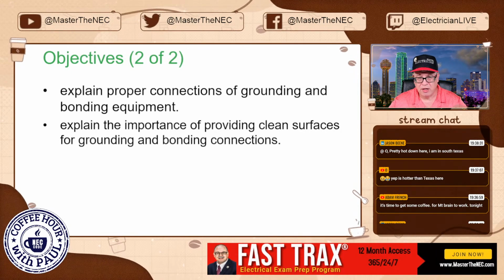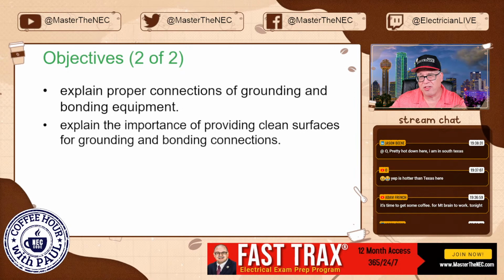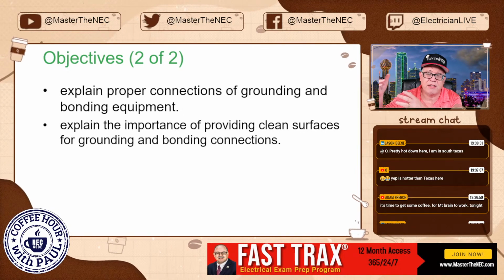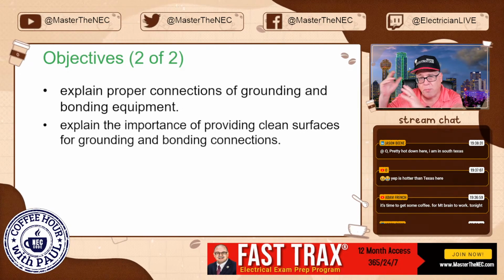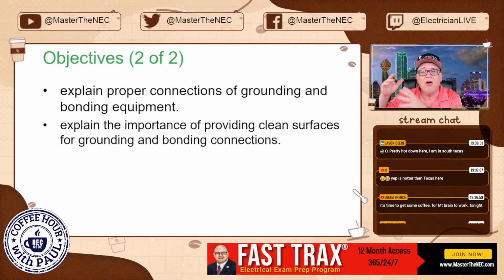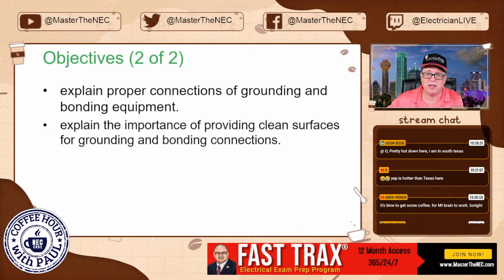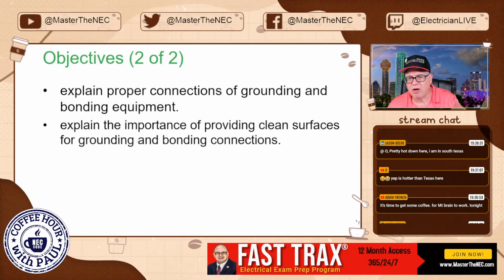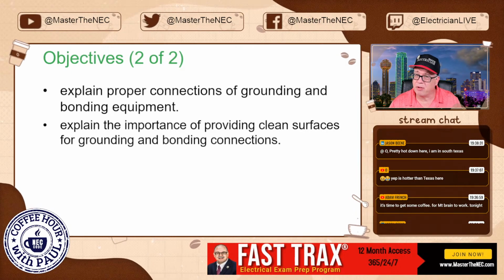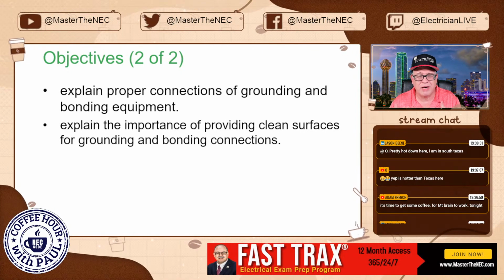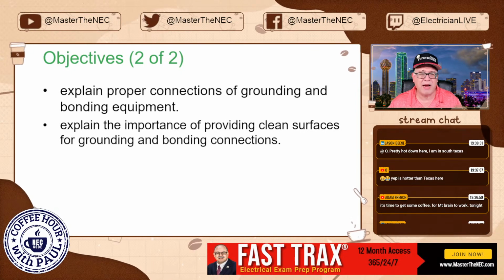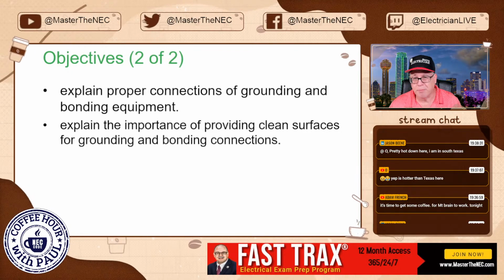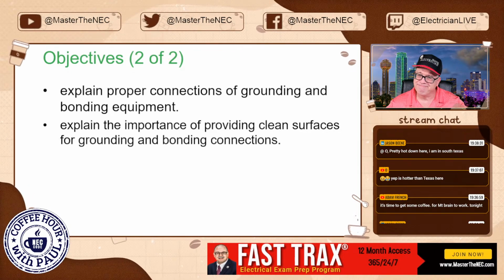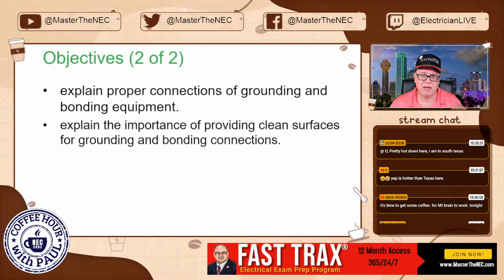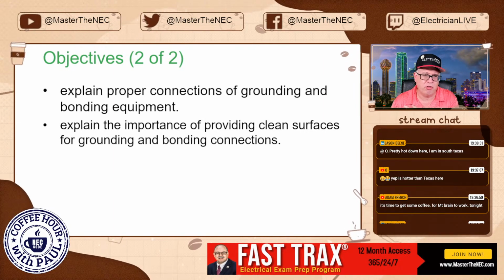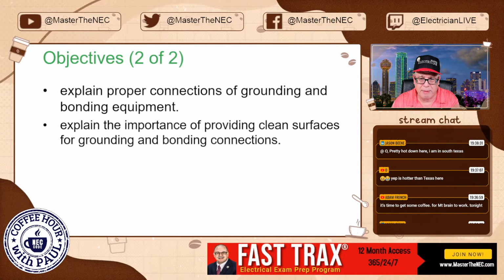Now, if we're talking about grounding and connection to earth, then we want transients, higher power lines contacting lower power lines, lightning, and surges, all of that, to get to the earth where it's intended to go. But when we talk about bonding connections in a building, we want to make sure that we're going to clear an overcurrent device. We want to make sure that we're adequately bonding components together. That's what bonding is, right? So we've really got to make sure those surfaces are clean. Make sure you wrench tight properly. Make sure you use the proper fittings where necessary, depending on your application.